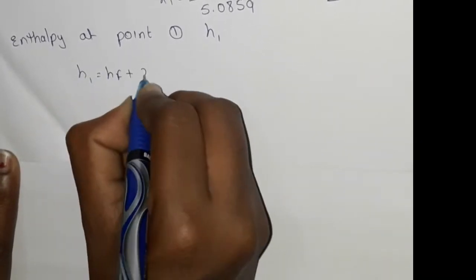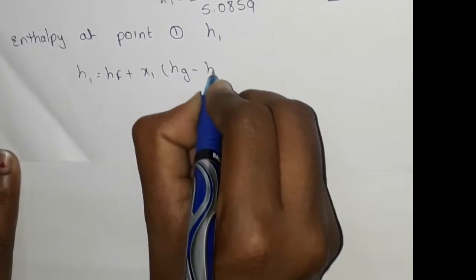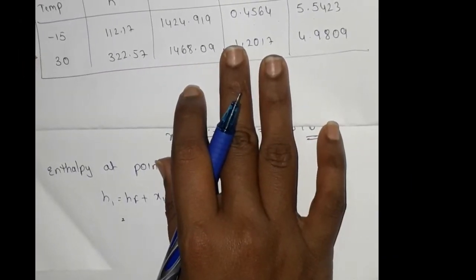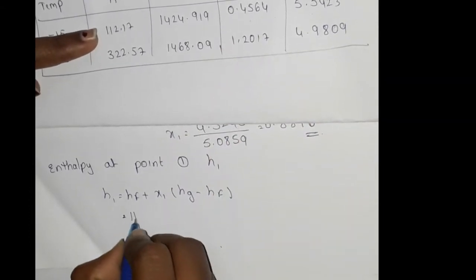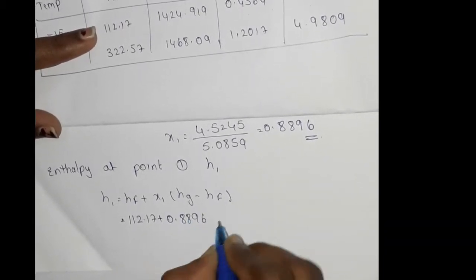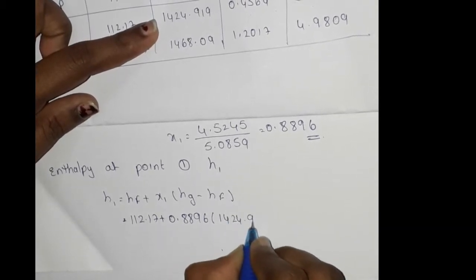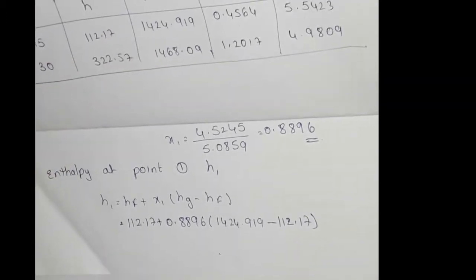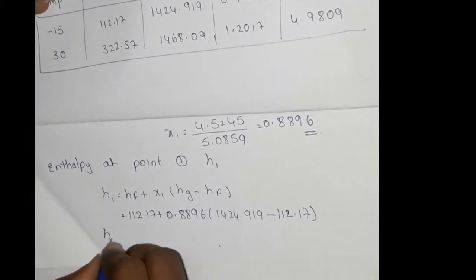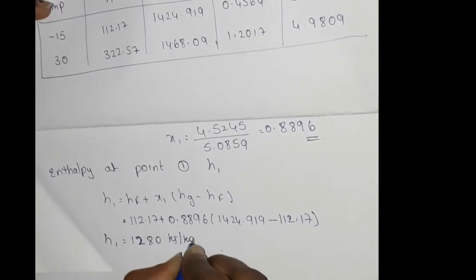Next, find enthalpy at point 1. H1 equals Hf plus x1 into (Hg minus Hf). At minus 15 degrees centigrade: Hf equals 112.17, x1 equals 0.8896, and Hg equals 1424.919. So H1 equals 112.17 plus 0.8896 into (1424.919 minus 112.17). Calculating, H1 equals 1280 kilojoules per kg.